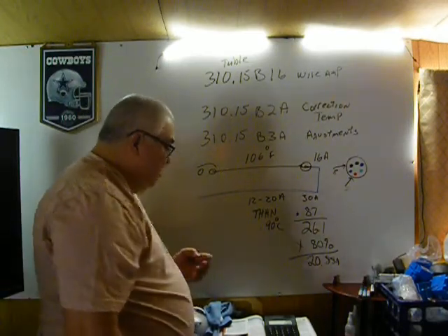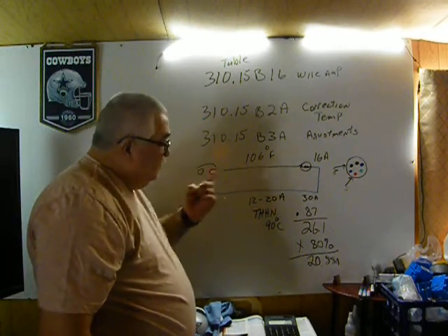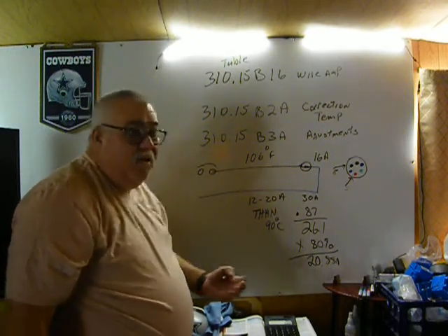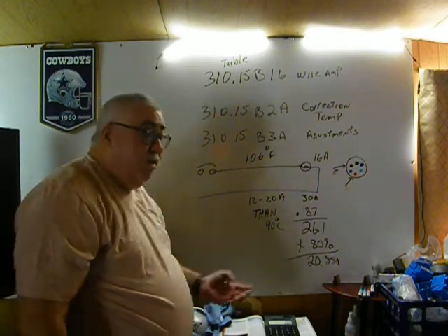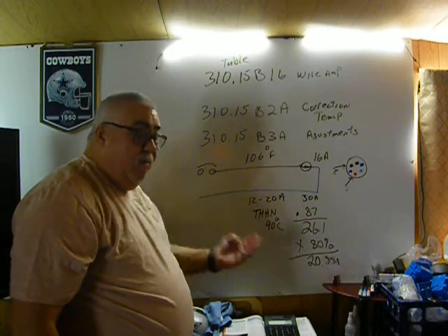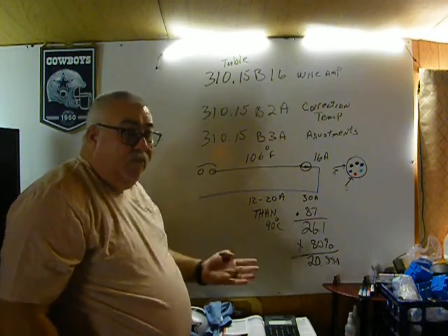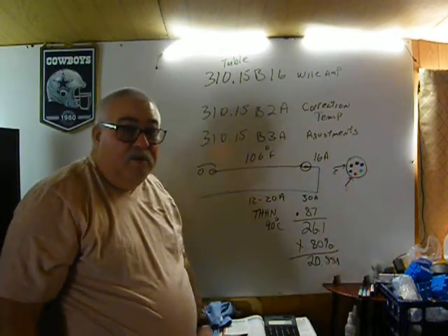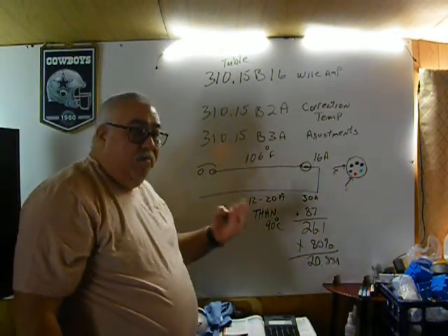In the code, they change it where it says conduits and raceway. Well, that neutral's not carrying current, then why do I have to count it? The ground's carrying no current. Ground's carrying no voltage. The only time it can carry voltage and current is if there's a short circuit or a ground fault. Boom! It should turn the power off, and you shouldn't have to worry about it because it's only carrying voltage and current for a short period of time for breaker trips.